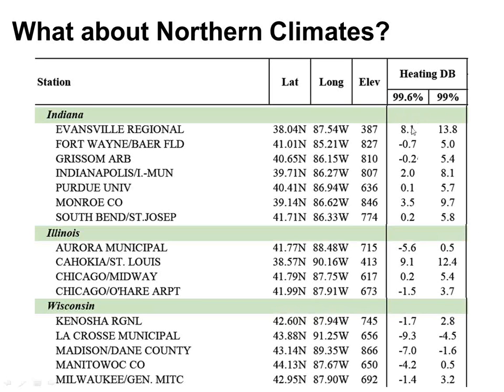So we don't really design for anything tighter than 0.4%. But if you pick either one of these columns, and let's go with the conservative one because I know that's what you guys are all going to do anyway, we'll go with the 99.6% column. If I go down to South Bend, Indiana, my design temp is 0.2. Basically, it's 0, right? So 0 degrees is what I should be designing my heating systems for in South Bend.